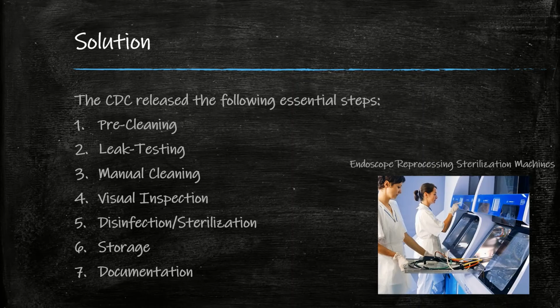Luckily, the CDC decided to take more of a process redesign approach. Instead of leaving it up to the hospitals to make their own sterilization requirements, in 2016 they sent out a list of steps that needed to be followed to clean the endoscope after the procedure. These steps were pre-cleaning, leak testing, manual cleaning, visual inspection, disinfection and sterilization, storage, and documentation. This procedure was great for reducing viruses, however it was lengthy and difficult for hospitals to achieve.